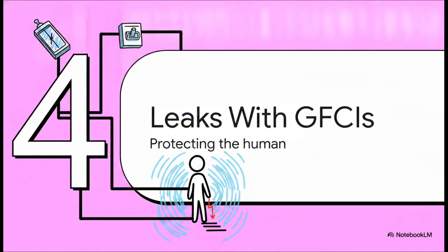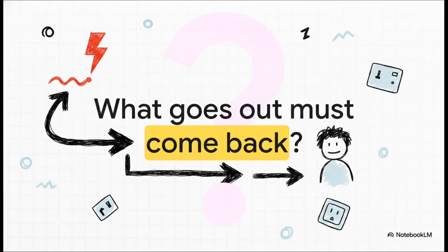Now, while fuses and breakers do a great job protecting your equipment from heat, they won't necessarily protect you. A standard breaker might not trip if a tiny, deadly amount of current leaks through a human body to the ground. That takes us to Section 4, catching leaks with GFCIs, protecting the human. The ground fault circuit interrupter, or GFCI for short, operates on a very simple yet incredibly crucial rule. What goes out must come back.